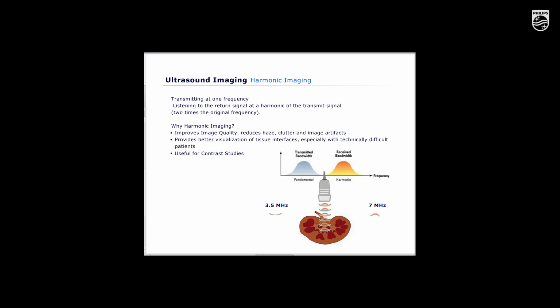An imaging mode that we have not mentioned previously is harmonic imaging. When in harmonic imaging mode, the system is transmitting at one frequency and listening to the return signal at a harmonic of the transmit signal. This is 2 times the original frequency. This picture shows a transmission at 3.5 megahertz and a received signal at the first harmonic of 7 megahertz. Note that these frequencies are just examples and not necessarily the frequencies used on the particular system.